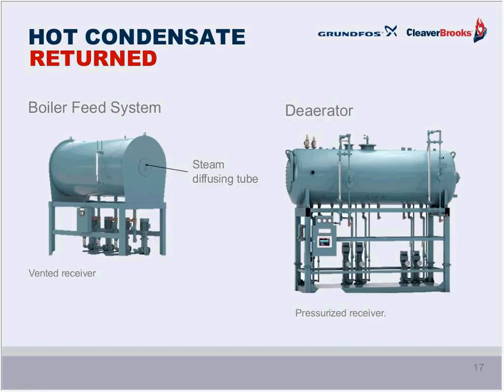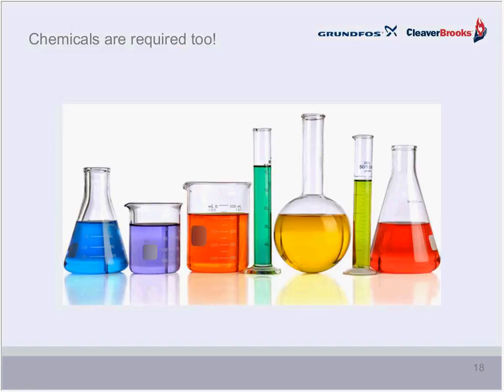For a more thorough job of O2 or oxygen removal, one should seriously consider a deaerator. Under pressure, normally about 5 pounds per square inch gauge, and the equivalent of 227 degrees Fahrenheit, these systems can remove oxygen to almost microscopic proportions, only about 0.005 cc's per liter. Okay, that's very much of what is involved with the mechanical removal of water impurities. But as I stated earlier, the total job has to be a combination of both mechanical and chemical means.